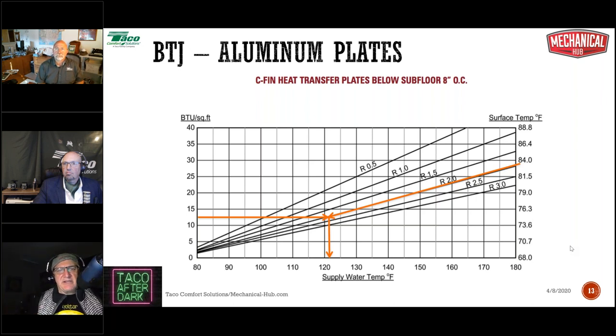The second stipulation is that the BTU per square foot load has to be consistent. It doesn't have to be the same, but they've got to be within a few BTUs of one another. So in this case, 13.4 BTUs. If I had a room that was 15 BTUs, that's close enough. If I had a room that was 11 or 12 BTUs, close enough. 25 BTUs, no, you're out of the pool. We can't play with you, all right?